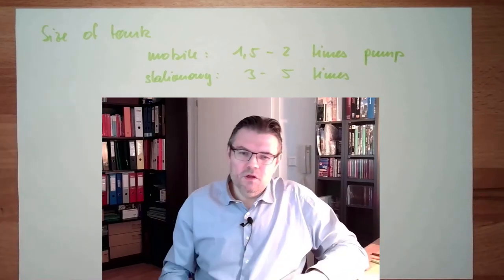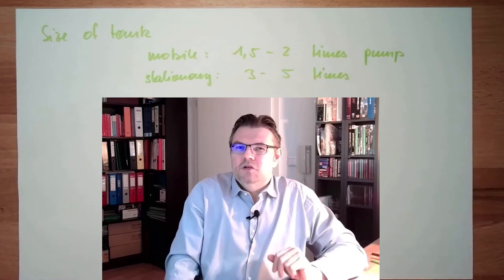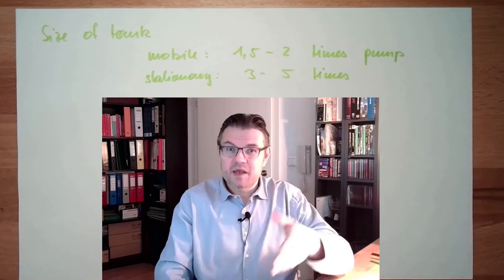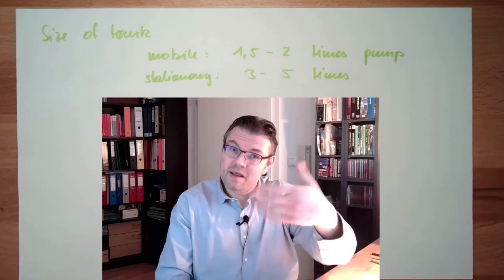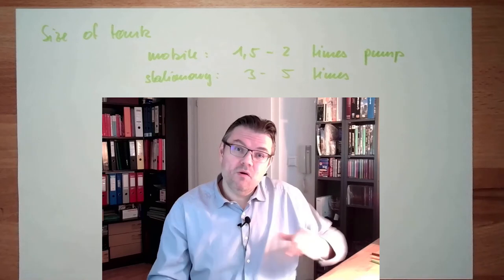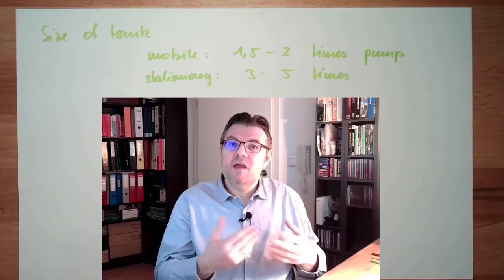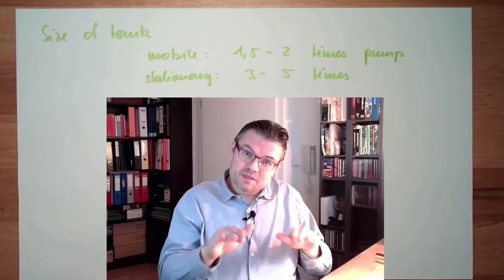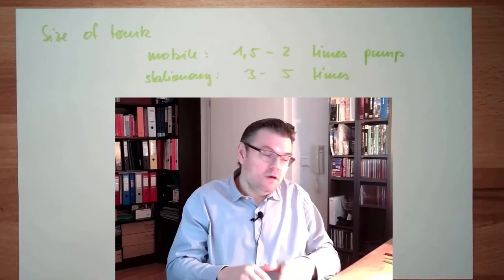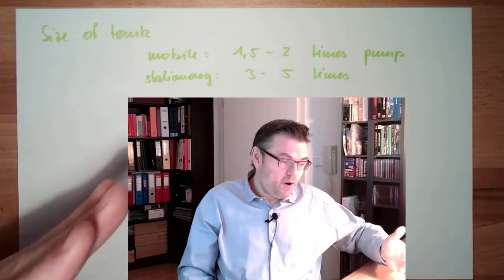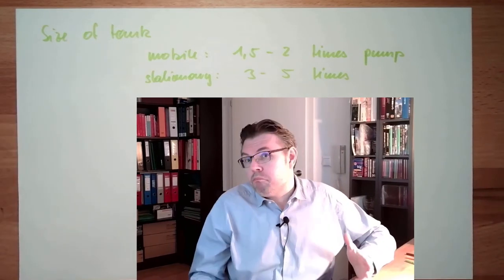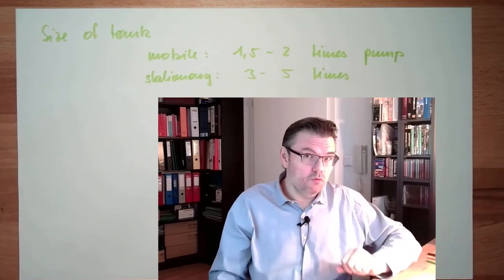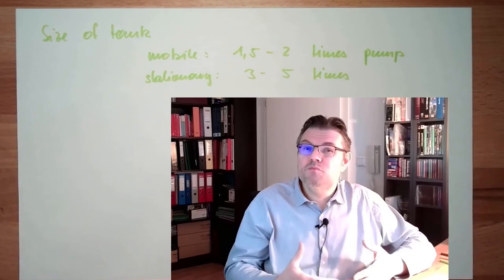Bigger is no issue because the oil needs time to relax, to cool. That's the main task of the hydraulic tank: cooling and also to get rid of air, to get rid of rubbish which should settle down. If you have place for a bigger tank, you can use a bigger tank. However, this amount of oil needs to be stored somewhere.